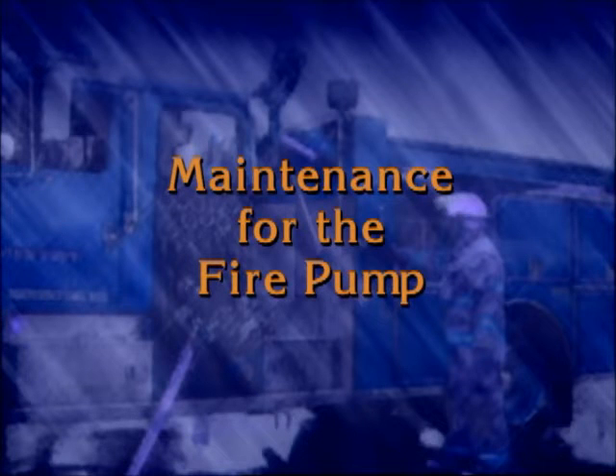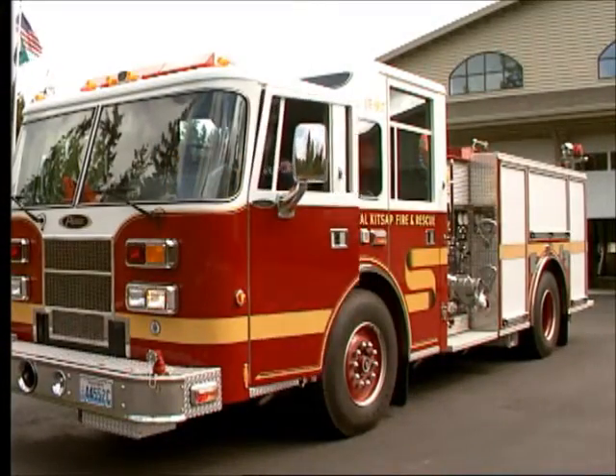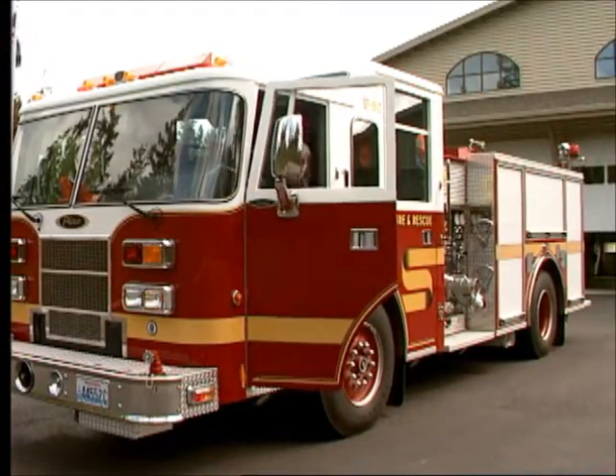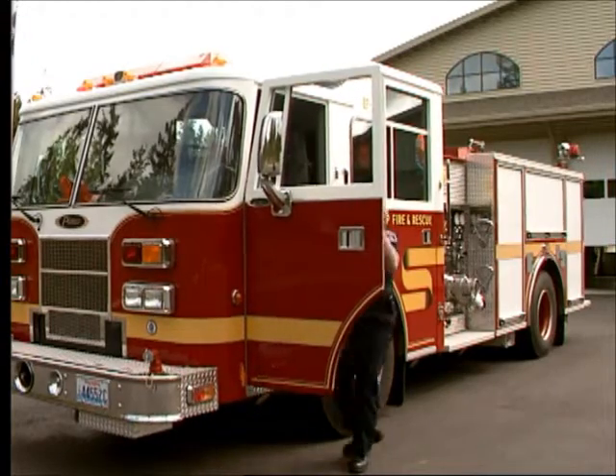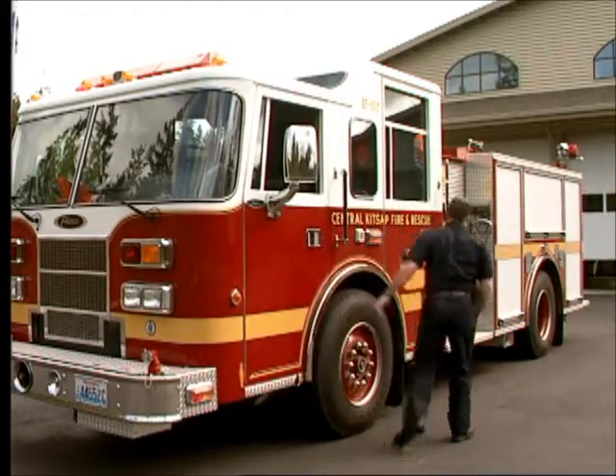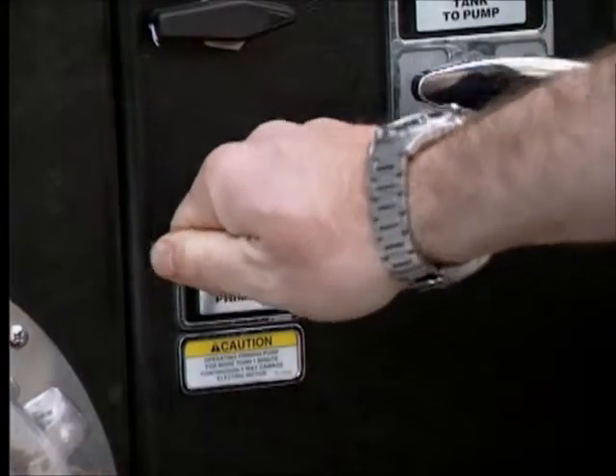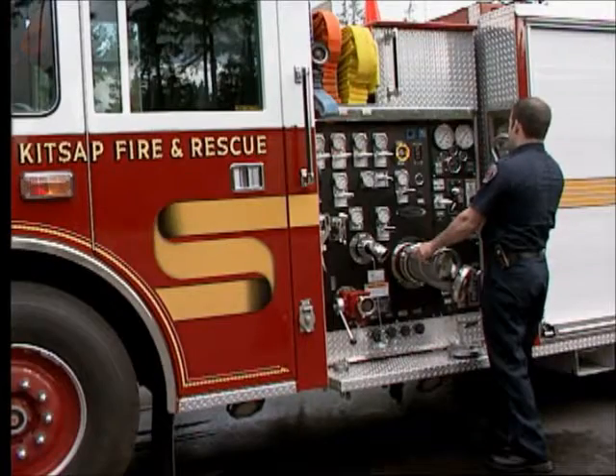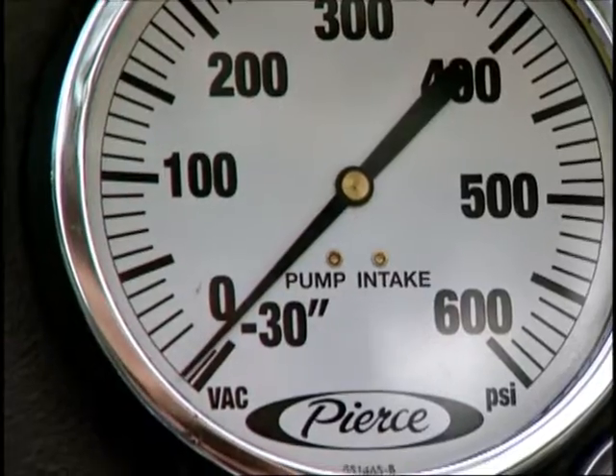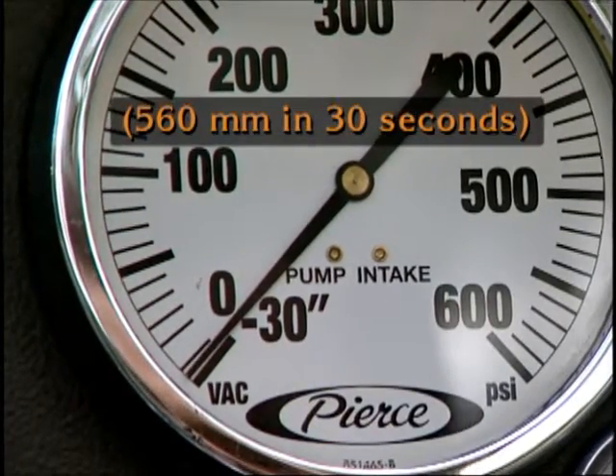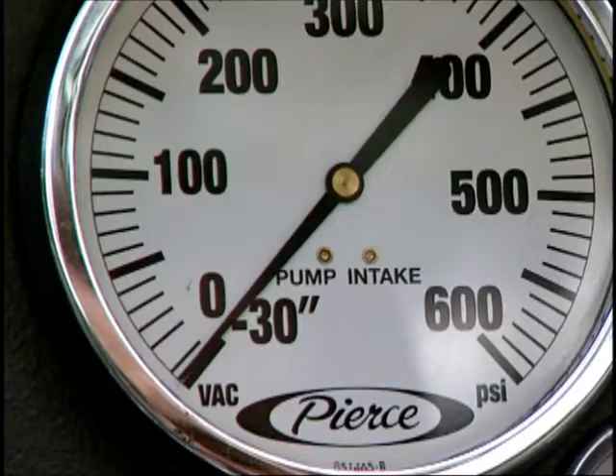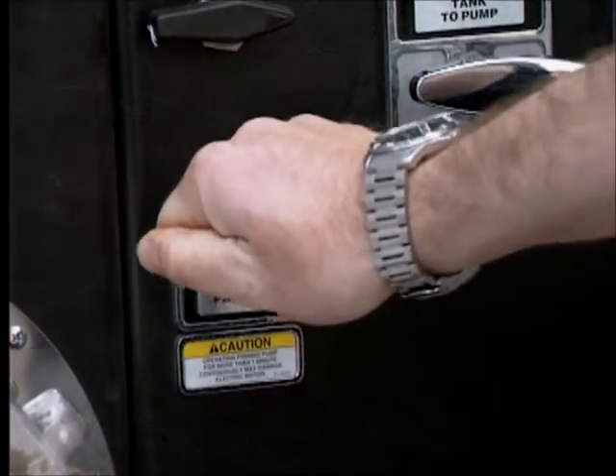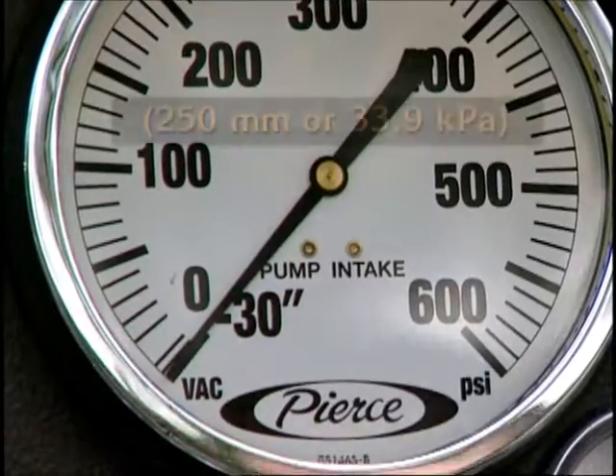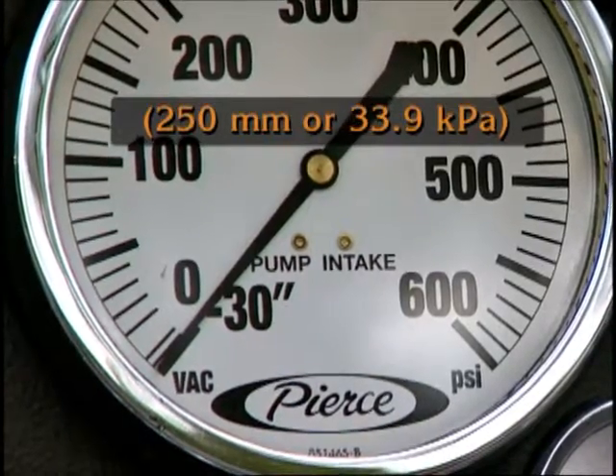Along with your maintenance schedule for the vehicle, you will need to establish regular preventive maintenance procedures for the fire pump. Such procedures will be helpful in prolonging the life of the pump, as well as detecting early signs of pump failure. Operate the pump primer with all pump valves closed and the pump dry. The intake gauge should read 22 inches of vacuum within 30 seconds. When the primer is released, the vacuum reading should not drop more than 10 inches in 10 minutes.